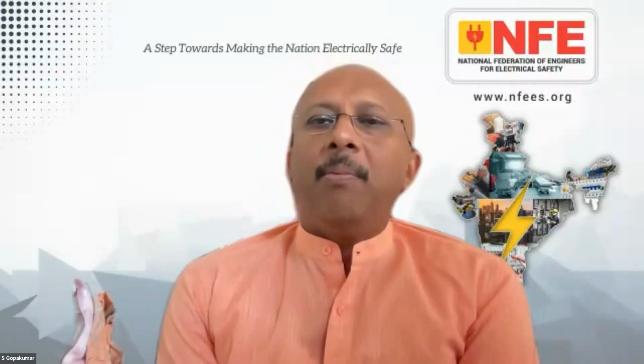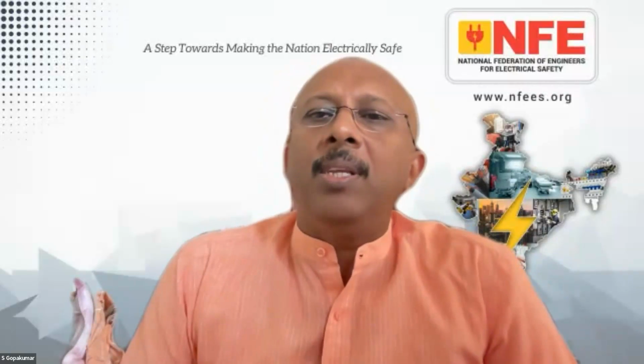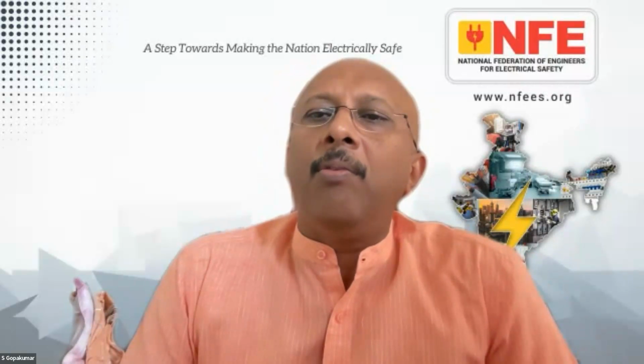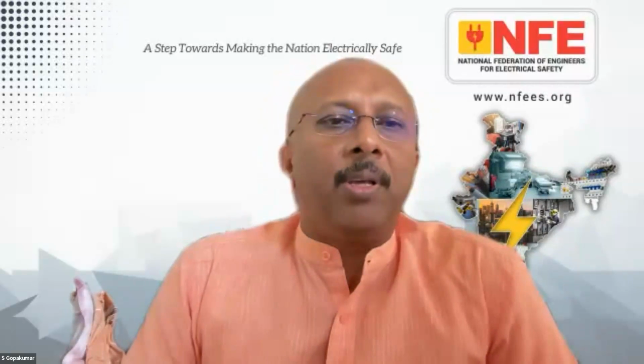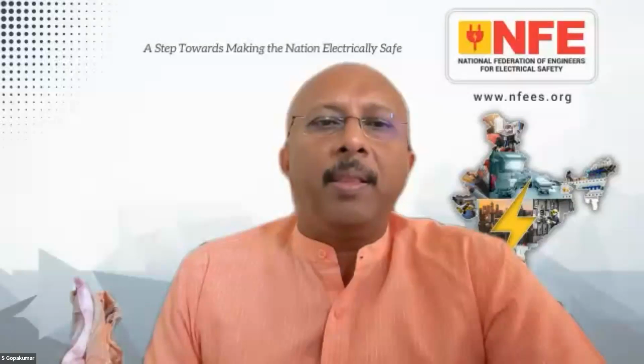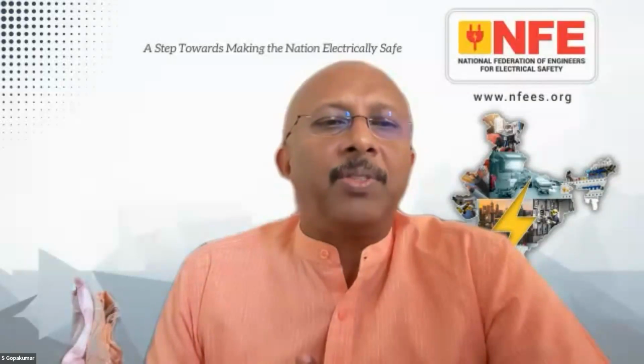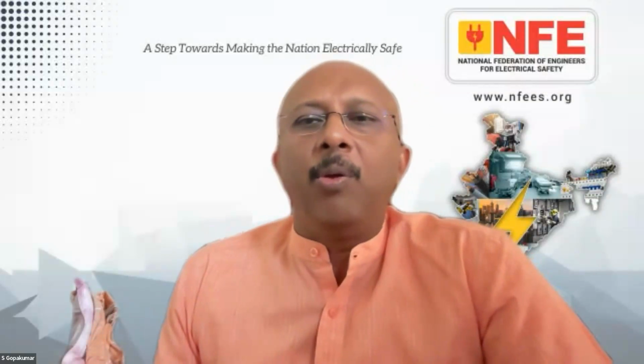Sir, then the question from Mr. Imran Maulavi. Vishnu sir, is it mandatory to use only copper cable for lifts, as most of the vendors ask for it? Not really. The sizing of the cable should be proper. If you use aluminum, obviously you need to use a higher size of cable because you won't have the same impedance. I don't think anywhere we are mandating copper wires as such. Okay, thank you. The answer is very clear. The proper sizes shall be used. It can be either copper or aluminum.